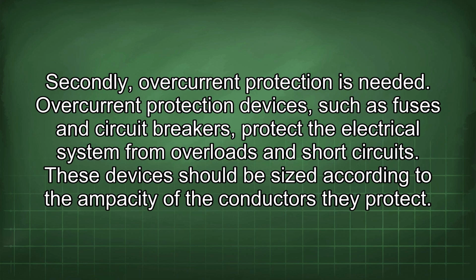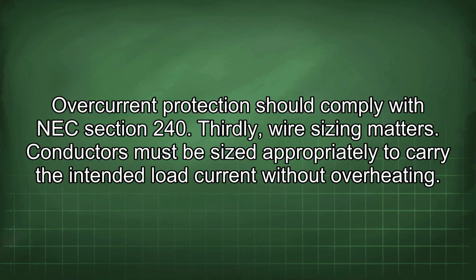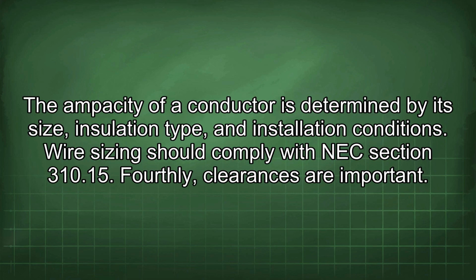Secondly, overcurrent protection is needed. Overcurrent protection devices, such as fuses and circuit breakers, protect the electrical system from overloads and short circuits. These devices should be sized according to the ampacity of the conductors they protect. Overcurrent protection should comply with NEC section 240. Thirdly, wire sizing matters. Conductors must be sized appropriately to carry the intended load current without overheating. The ampacity of a conductor is determined by its size, insulation type, and installation conditions. Wire sizing should comply with NEC section 310.15.